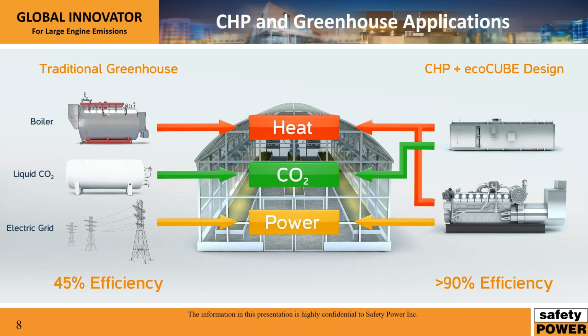An alternative approach is to use a natural gas or other gas-burning genset as your primary power source. This removes reliance on the grid and provides power, usually at lower cost. If used strictly for power generation, a modern natural gas engine should output an efficiency of around 45 to 50%, depending on the engine, where the majority of the energy is lost in the form of heat.